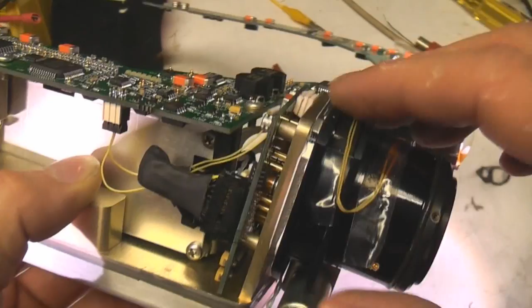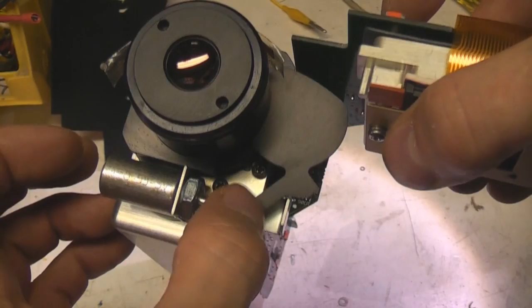And then there's the actual camera headboard here, and you can actually see now how the shutter works. Just a solenoid that pulls that shutter into there. Incidentally, the lenses of these things aren't glass or anything, because the long wave infrared doesn't go past those. This has actually got a germanium lens. There's only about 3 materials that will transmit that waveform. There's germanium, zinc selenide and sodium chloride, common salt. Obviously salt has some slight lifetime issues when it gets wet, but I think germanium is pretty much the standard for most thermal imaging applications.